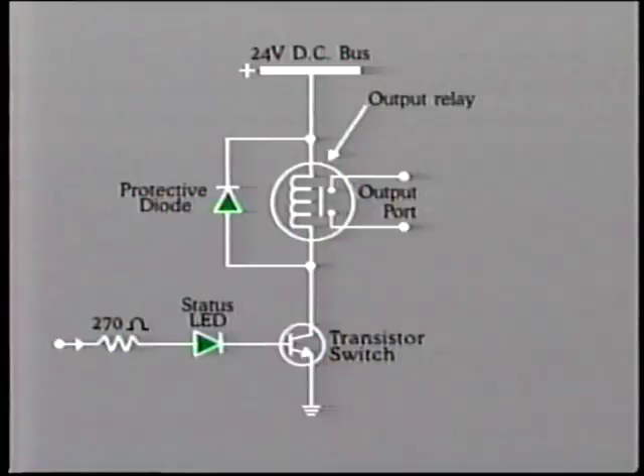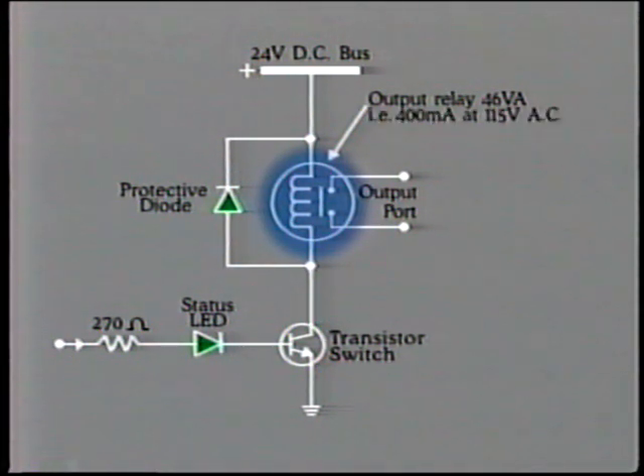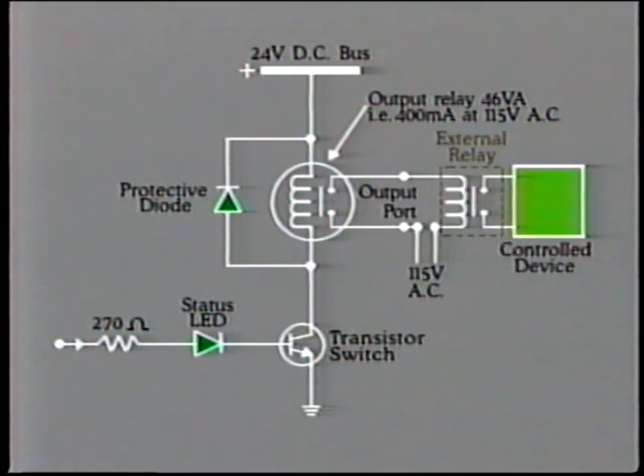The biggest problem, however, is the limited capacity of the output signal. These output relays are usually quite small, with a maximum capacity of, say, 46 VA. That means that with an applied voltage of, say, 115 volts, our output current would be limited to 400 milliamps maximum. Of course, an external relay can always be installed if heavier current is required by the control device.